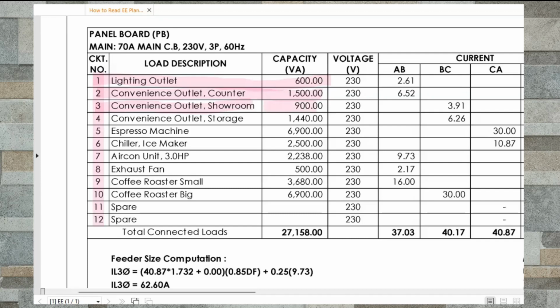Yung number 4 is for convenience outlet na nasa storage. Number 5 is yung espresso machine. Meron siyang capacity na 6.9 kVA. Yung number 6 is chiller or sinama na yung ice maker. Yung number 7 is ito yung circuit breaker para sa ating aircon. Meron siyang rating na 3 horsepower. Yung number 8 is intended for exhaust fan. Yung number 9 is coffee roaster small. Yung number 10, circuit breaker to na sa big coffee roaster din. Itong 11 at saka 12 is ito yung spare. So sobra to or pwede mong gamitin for expansion, para sa mga additional na kakabit na mga loads.